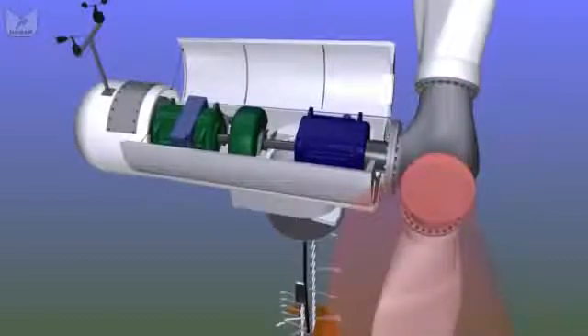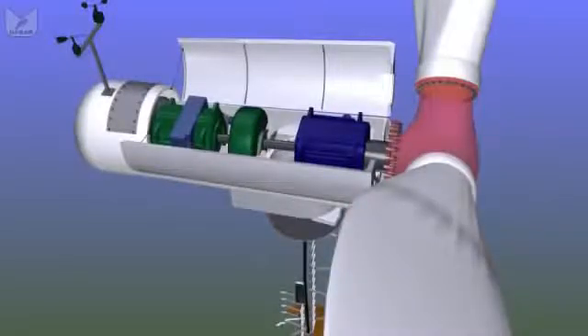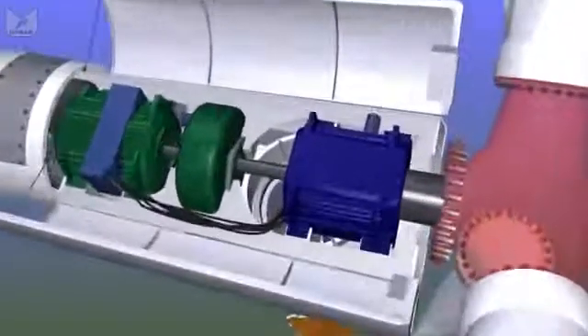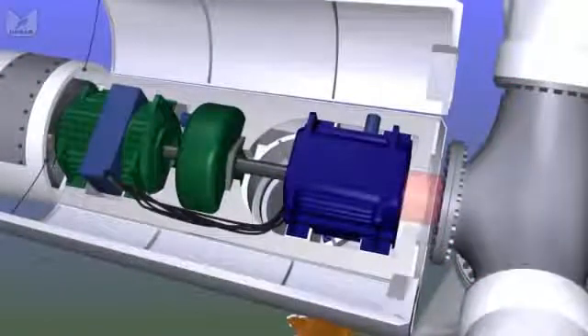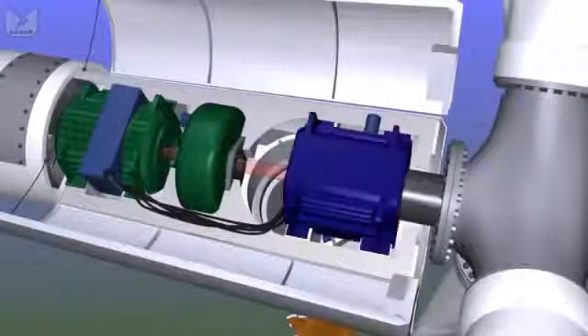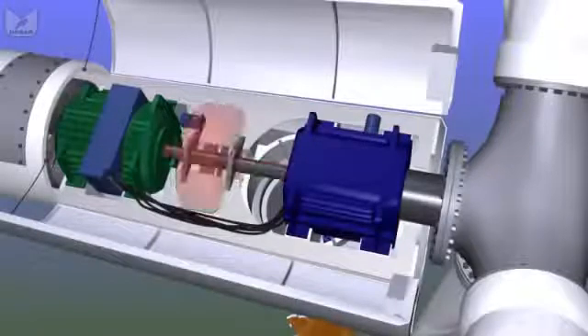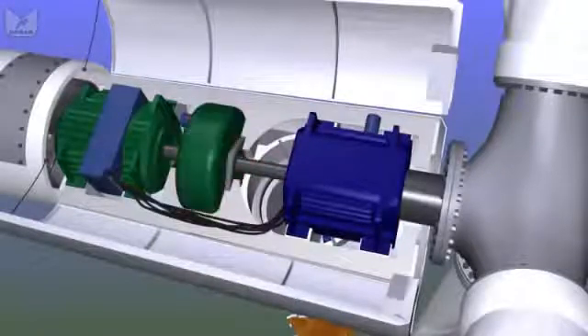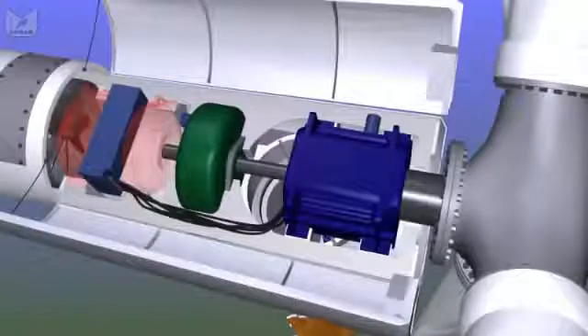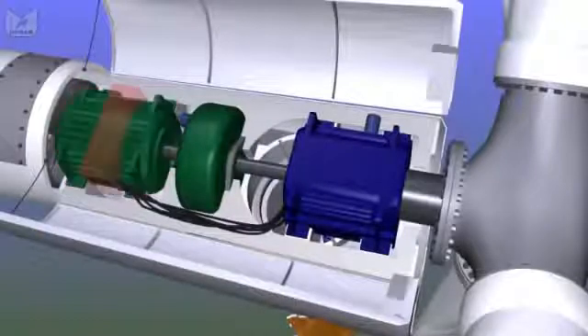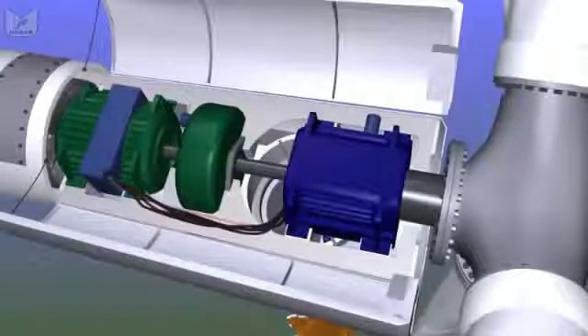The blades can turn, or pitch, so that the angle they form with the wind can be varied. Out of the back of the hub, we have a shaft which leads into the gearbox, then a high-speed shaft, through a brake, into a generator. That generator then supplies the electrical power at about 690 volts, all the way back down the tower to the base.